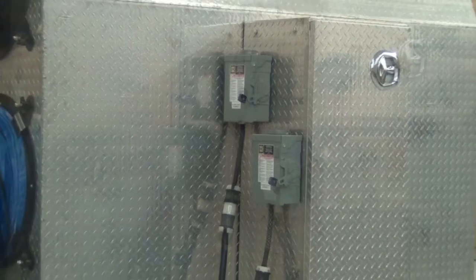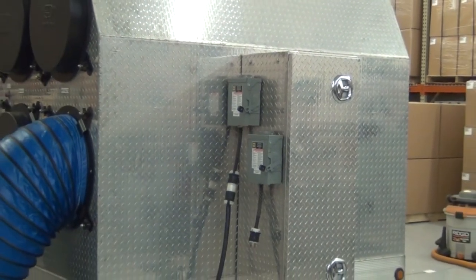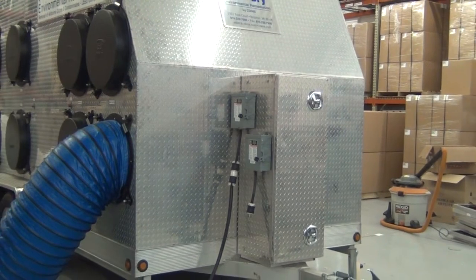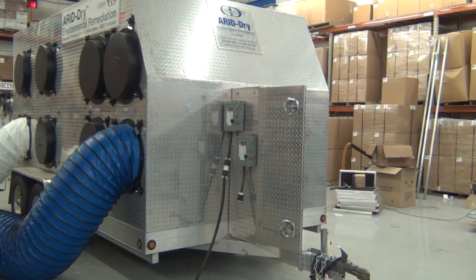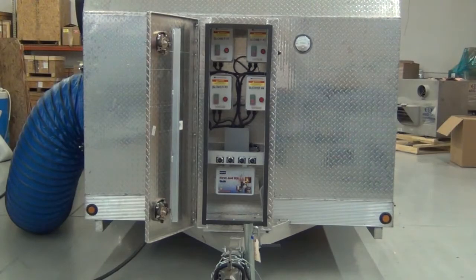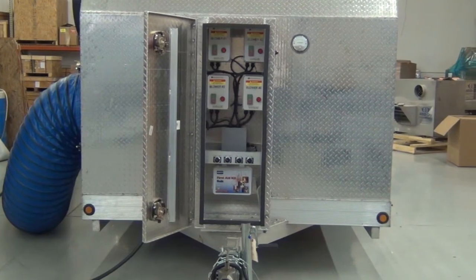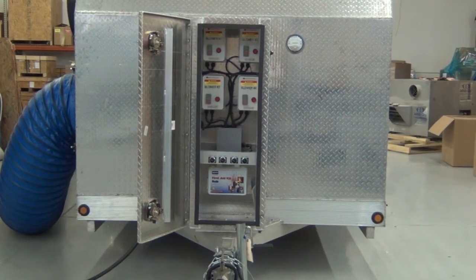The disconnect switches are mounted on the control panel for the system, which houses the individual motor starters and operational switches. For our example here, we've attached 1 return duct and 1 supply duct to the system. This will allow for approximately 4,000 to 5,000 CFM through the filtration system. When the front control panel is open, you can see the 4 motor starters that control motors on blowers 1, 2, 3, and 4.